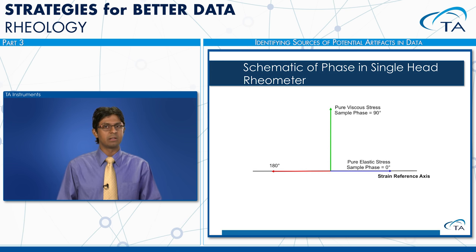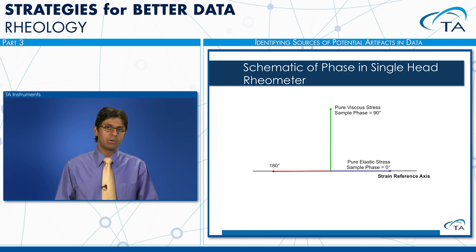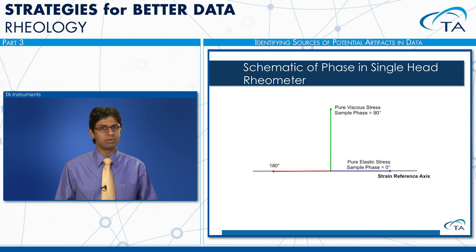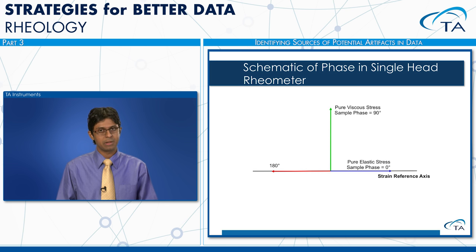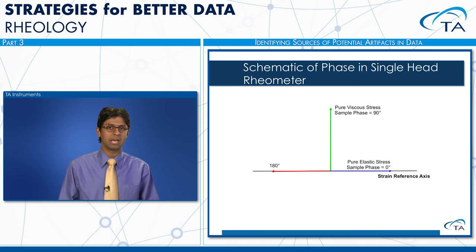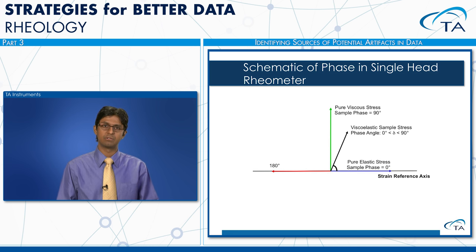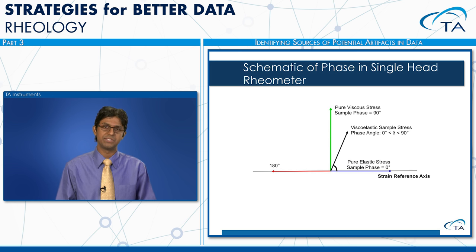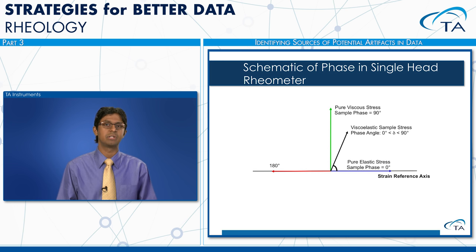When looking at the phase angle in a single head rheometer during an oscillation experiment, there are two possible cases. For a perfectly elastic material, the phase angle is zero degrees. For a perfectly viscous material like a fluid, the phase angle is 90 degrees. For a viscoelastic material, the phase angle is somewhere between zero and 90 degrees — the closer to zero, the more elastic; the closer to 90, the more viscous or liquid-like.